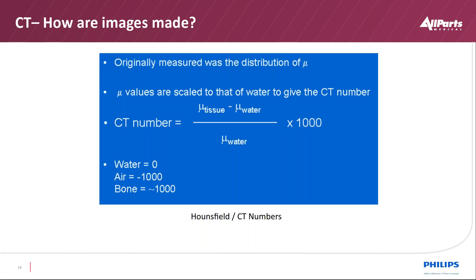So I've seen phantoms sometimes topped off because they get an air bubble or something with tap water, and you see things growing in that phantom. We always try to make sure when we are servicing a CT scanner that water is a known quantity. So if we don't know what's in that phantom, we'll pour it out. We'll put distilled deionized water in it, and then verify our calibrations. Bone is emulated by a material called Teflon in most cases, so that's in the high 900 range for CTs.